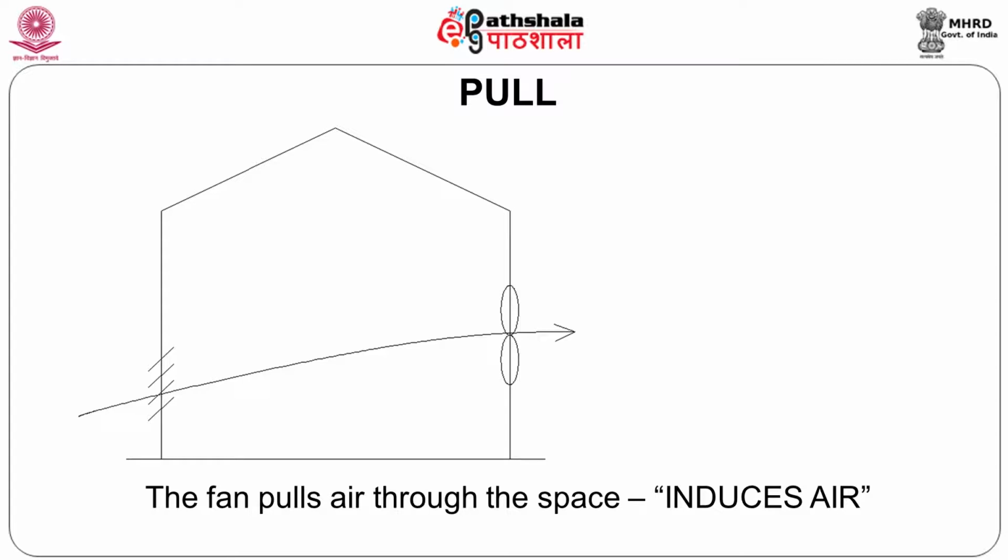This is a very simple detail like one sees in any toilet. You go to a toilet, you find that there is a small exhaust fan throwing out air. That is called pull ventilation. Ideally for such an application, air inlet comes in from the door, the exhaust fan maintains the place at a negative pressure and throws out the vitiated air. Toilets are a very simple example of this, and a prime requirement is that the place should be reasonably airtight.